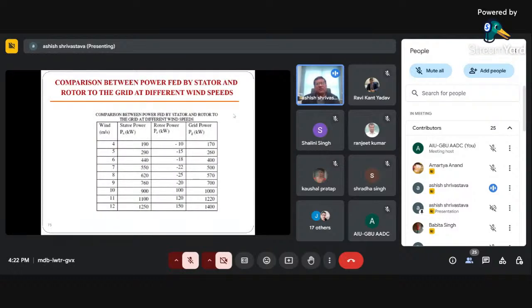This is just a comparison of how the power is flowing from the stator to the grid, or from the grid to the rotor. The negative sign ensures that power is being taken by the rotor up to here, and after that the rotor is also supplying power to the grid side. So both are supplying power on this side. That's why the sum of these two is equivalent to this. So stator and rotor both have power flow.